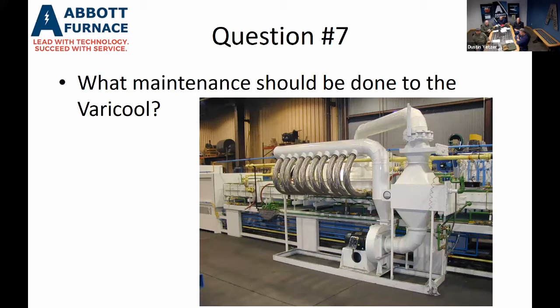Another maintenance point or a thing to keep an eye on is the housing, the shaft between the motor and the fan. We put a seal there where we run a very small amount of nitrogen on that seal. As that seal wears, it's set with a regulator to increase that nitrogen flow. And over a period of time, when that nitrogen flow gets excessive, you're going to have to go in and replace the seals between the motor and the fan housing.